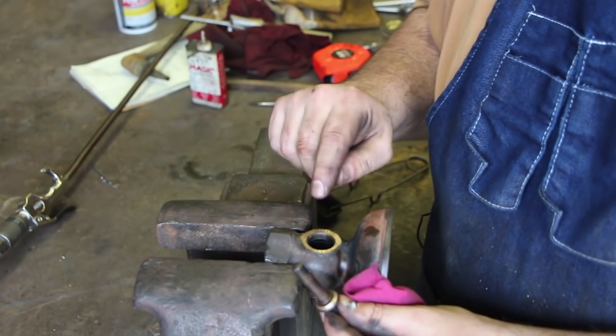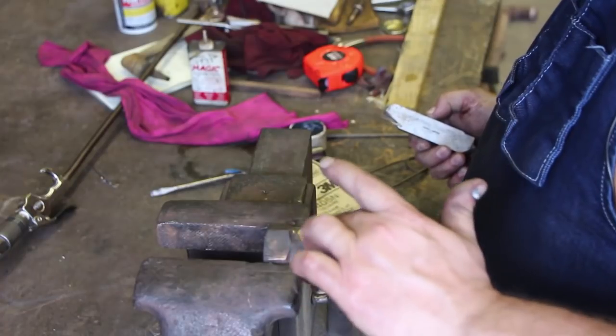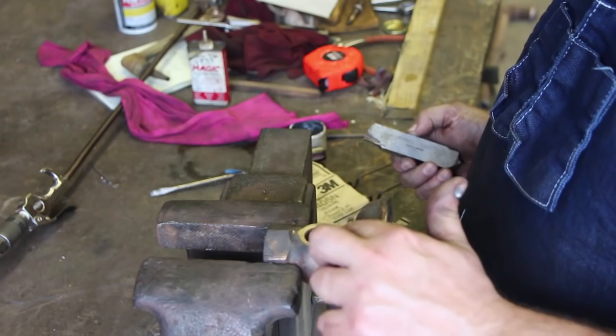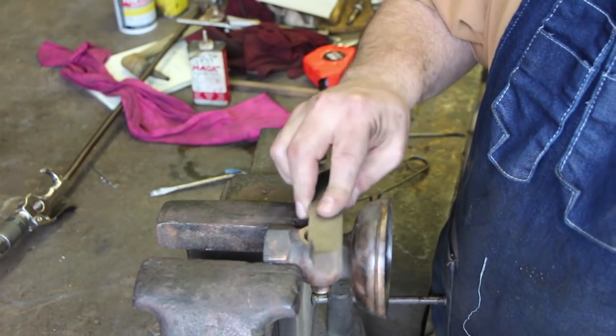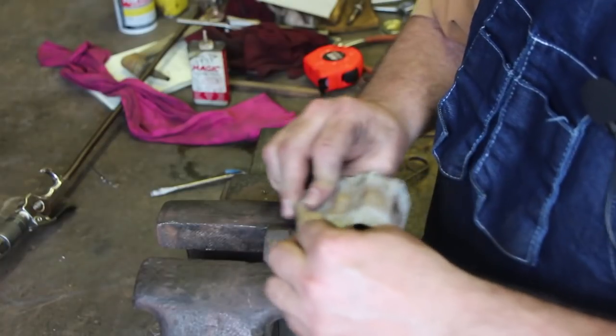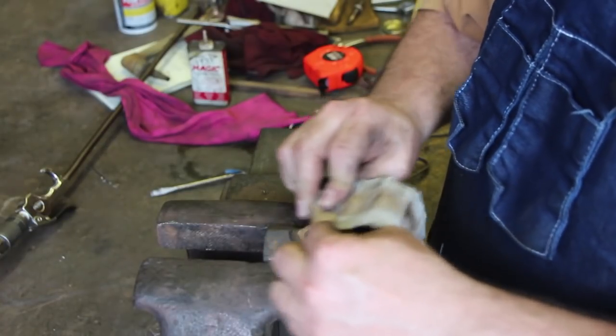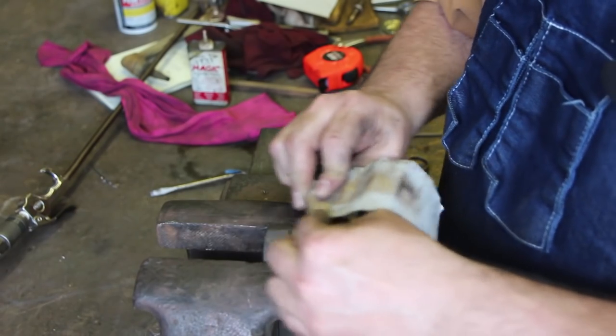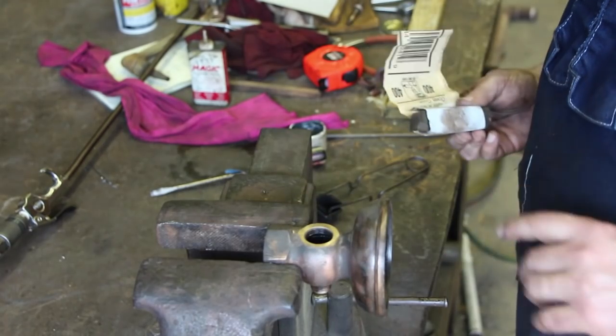The next thing I'm going to do is take some lapping compound and put it on this valve. We're just going to make sure we've got a good seat on here. Since we've got it apart, we might as well lap that valve in to make sure we got a good fit. I've got a little bit of coarse lapping compound on there and I'll drop that valve down in there. I've actually already done some of this, and you can see I've got a nice clean surface on there. I'm also not very satisfied with the surface from that cutter — it left a bit of chatter mark — so I'm taking a flat piece of high-speed steel with very fine sandpaper and just lapping this in place right on the part to smooth out that rough surface.